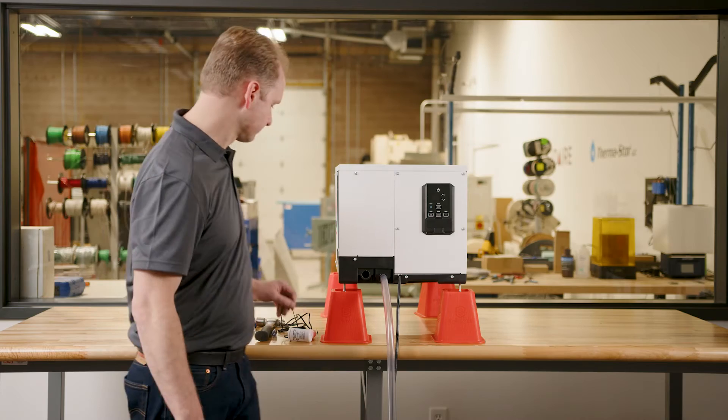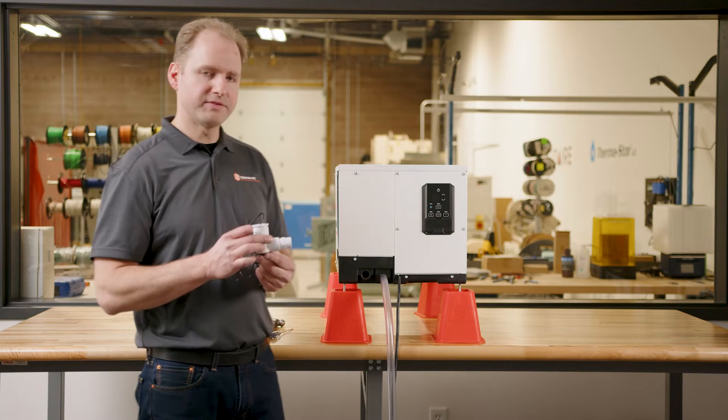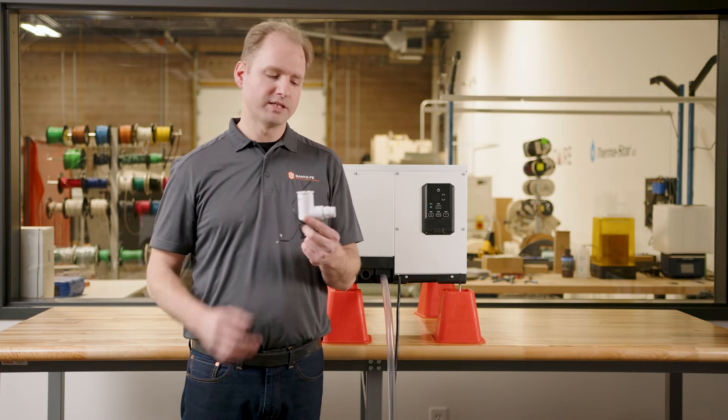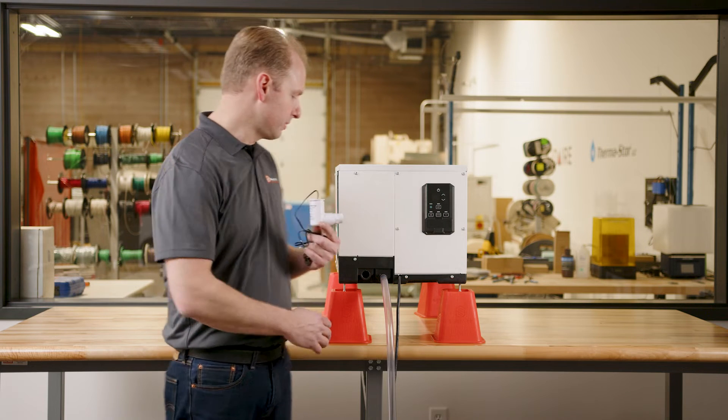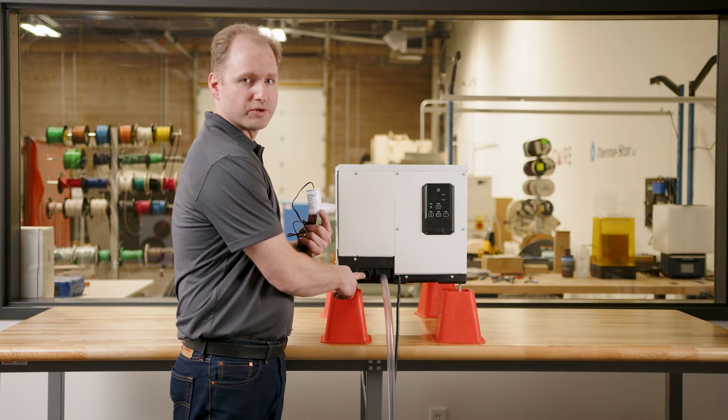In this next step we'll install a safety float switch. If the main drain line becomes plugged, the safety float switch will turn the unit off, preventing flooding. The safety switch we're using here has a three-quarter inch thread that we'll thread into this secondary drain port.